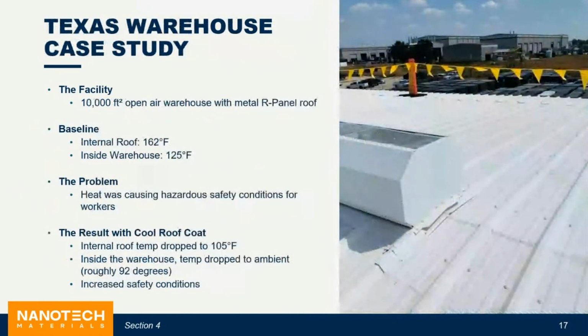Sometimes it's not about energy, though. It can be about safety and comfort. I know OSHA has some heat mitigation laws that are now in place, and depending on the state, you might be required to keep the internal non-climate-controlled space at 90 degrees. So we've done a case study here in Texas, which was an open air facility. This building has no air conditioning. There's no thermostat to turn down, no systems to optimize. The roof really is the cooling system, along with some fans. That's why this one's such a clean test. We changed the roof and nothing else.